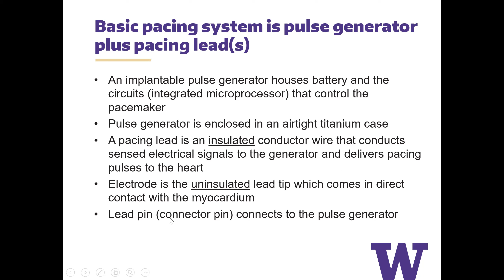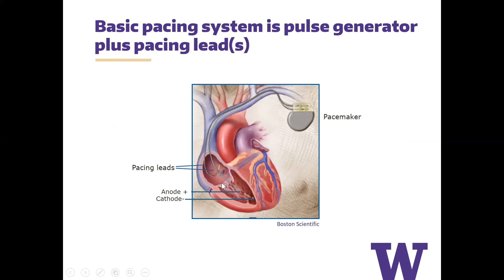So this is a schematic. Here you have a pacemaker generator, and you have 2 wires in this case. Up here will be the connector pins, and leads and wires are used interchangeably. They'll go down, this lead ends up in the right atrium, and this one ends up in the right ventricle. What they're showing you here is a bipolar right ventricular lead. So you have an anode and a cathode. Down here will be the lead tip, the part that's not insulated, which comes in direct contact with the myocardium. And the rest of it is the conductor.